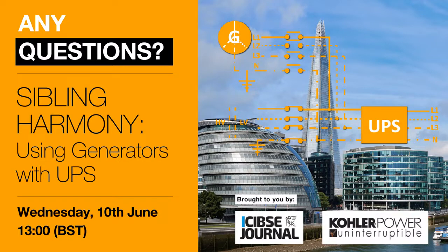Yeah. Using fossil fuels, we do have cleaner burning engines, being tier 3 and stage 5, but non-fossil fuel, as in gas, LPG. We do have an arm called Clarke Energy that uses gas generators, but they're generally much larger generators. At the moment, there's no hybrid system coming along that SDMO are doing, other than wind, solar, conventional systems. It's not available at the moment. We're still using fossil fuels because it's 100% reliable. 7 seconds and your generator is online using fossil fuels. But we've also got much newer options, the generators themselves are much cleaner, even the modern engines, and also with the scrubbing exhaust and things like that.